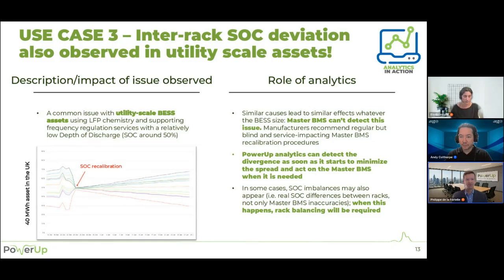And in this example, with a larger asset in the UK, it's almost a perfect storm. The state of charge recalibration took place, all the numbers converged into one single value, and then just afterwards all the racks, all the master BMSs, indicated a diverging number in terms of the state of charge in the system. This is a common issue, especially when the depth of discharge of systems is relatively low, typically systems supporting frequency regulation services, because they don't recalibrate themselves easily by hitting low or high SOC ranges. So the divergence becomes larger and larger over time. It's striking to see those similar phenomena in smaller or larger systems.